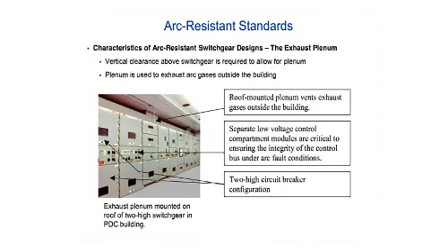The plenum construction, and I show this inside a PDC because it's important to recognize that one of the design elements, if you're putting metal-clad arc-res switchgear inside a building, you have got to allow for the plenum height. Plus, see this little box right here?